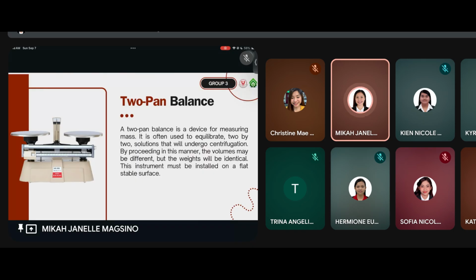So for the two-pan balance, a two-pan balance is a device for measuring mass. It is often used to equilibrate 2 by 2 solutions that will undergo centrifugation. By proceeding in this manner, the volumes may be different, but the weights will be identical. This instrument must be installed on a flat, stable surface.